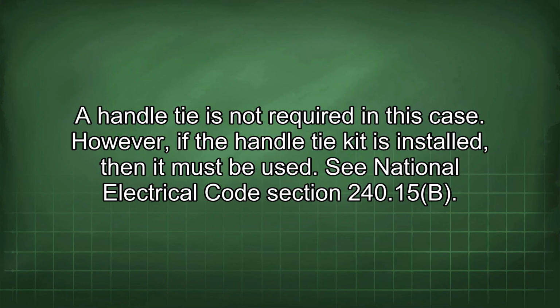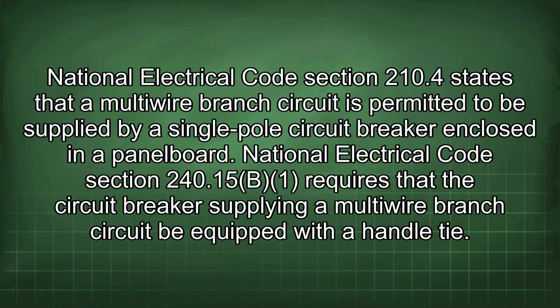A handle tie is not required in this case. However, if the handle tie kit is installed, then it must be used. See National Electrical Code Section 240.15(B). National Electrical Code Section 210.4 states that a multiwire branch circuit is permitted to be supplied by a single-pole circuit breaker enclosed in a panel board.